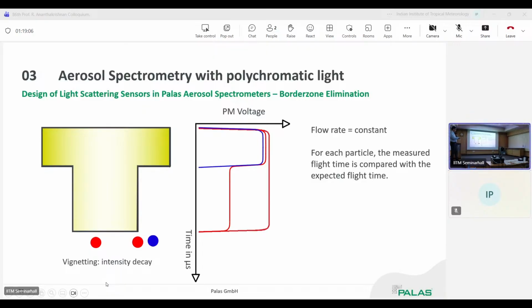If those particles were in the outer area, they produce a very small signal in height, still more or less similar to what we see from those particles passing here, maybe slightly lower, but the signal length from here to here is short. Time of flight is short. And if we have a particle passing at the outer zone, the signal is even lower, and we only see the time of flight from here to here. And with that, you can clearly identify whether a particle passes in the middle by the time of flight. The expected time of flight is according to the measured time of flight, with some tolerances, of course. And for those particles whose time of flight is too short, we have to decide what we do with them. Some of them we can still evaluate, others we just discard.